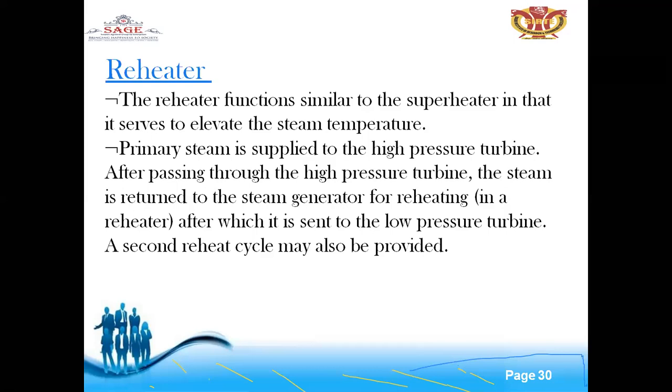Reheater function is similar to the superheater in that it serves to elevate the steam temperature. Primary steam is supplied to the high pressure turbine. After passing through the high pressure turbine, the steam is returned to the steam generator for reheating in a reheater, after which it is sent to the low pressure turbine. A second reheat cycle may also be provided.